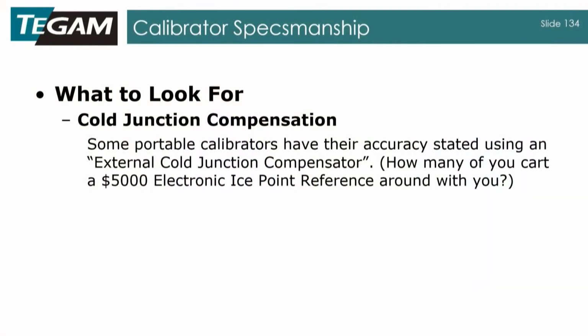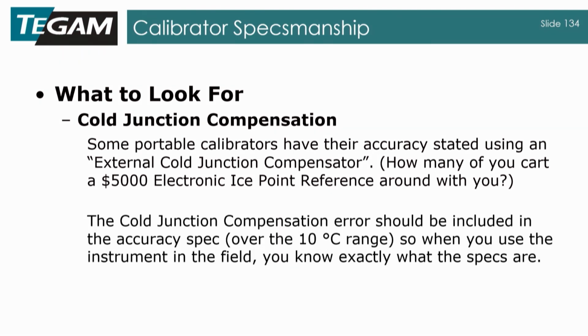Cold junction compensation is another thing to look at. A lot of the stated accuracy in a calibrator excludes that, so to actually get that accuracy you need to use an external ice bath. That's a pain to walk around with, so you really want something with cold junction compensation built into the specifications. That was something we spent a lot of time on when developing our new calibrator—how to lower the uncertainty of the cold junction compensation so you don't have to use an ice bath, and so we can meet the requirements. Our goal was for it to be used as a portable secondary standard under AMS 2750E.